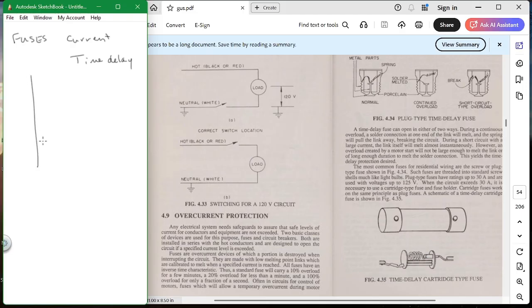So basically what you want is this trip curve, I versus T. You have one that goes like this, and another, and another, and another. This should be the farthest one upstream, this should be next, and this should be the farthest one downstream. You should be able to overlay your current versus time graphs of your fuses, and this should be the one that trips first, then second, then third, then fourth. If you get these backwards, what happens?